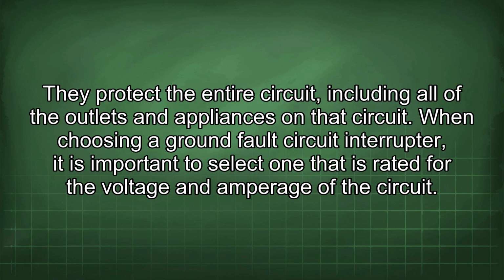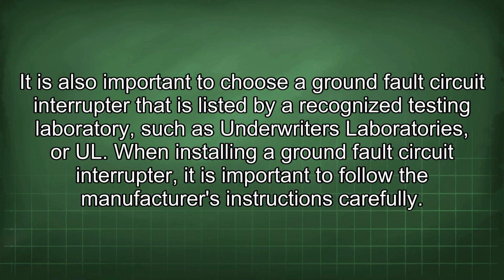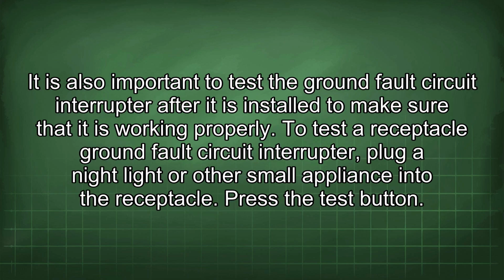When choosing a ground fault circuit interrupter, it is important to select one that is rated for the voltage and amperage of the circuit. It is also important to choose a ground fault circuit interrupter that is listed by a recognized testing laboratory, such as Underwriters Laboratories, or UL. When installing a ground fault circuit interrupter, it is important to follow the manufacturer's instructions carefully. It is also important to test the ground fault circuit interrupter after it is installed to make sure that it is working properly.